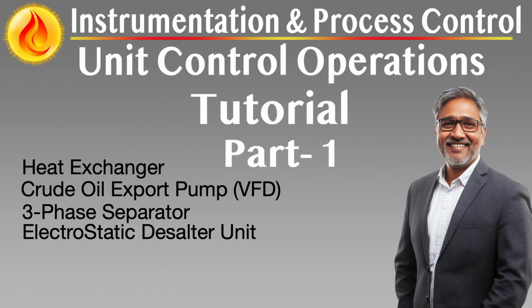Traditional fixed-speed pump systems required throttling via control valves to maintain pressure or flow set points, leading to significant energy losses and mechanical stress. VFDs address this by allowing the motor speed to match precisely the required hydraulic load. This is particularly beneficial in long-distance export pipelines where back pressure, temperature-induced viscosity changes, and terminal tank levels can shift continuously. By modulating the motor frequency, VFDs reduce power draw during low demand and ramp up smoothly during high flow periods, improving both operational stability and life cycle efficiency.